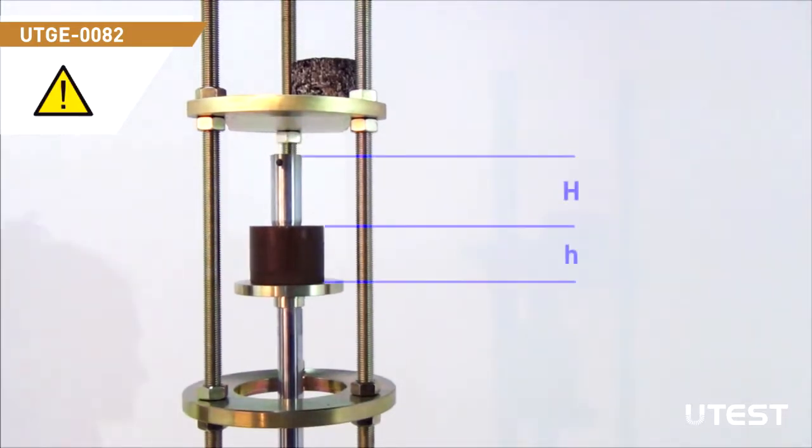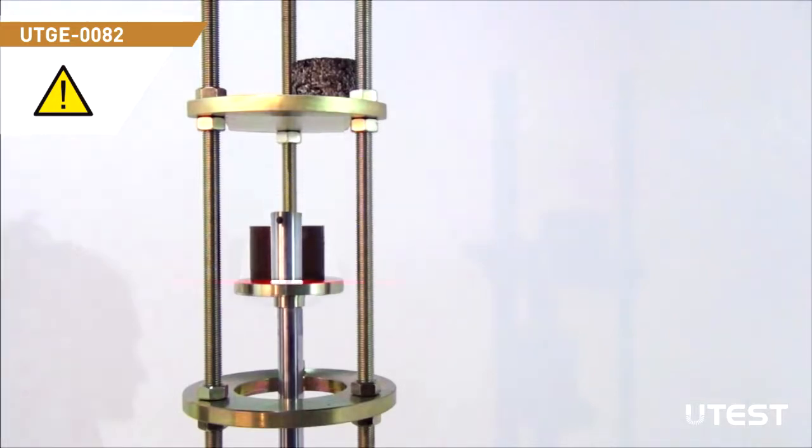If the height of the sample is shorter than the height of the cutter, the operator may not estimate when to stop because the cutter will be embedded to the sample. This may result in a stuck cutting collar and a damaged sharp edge.